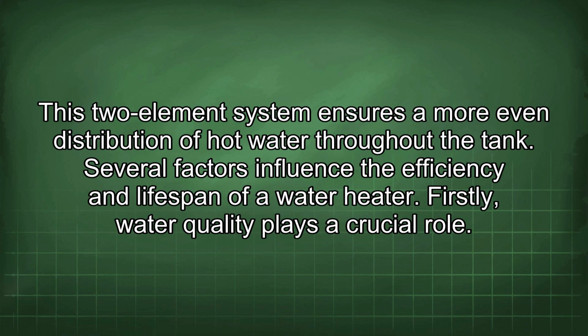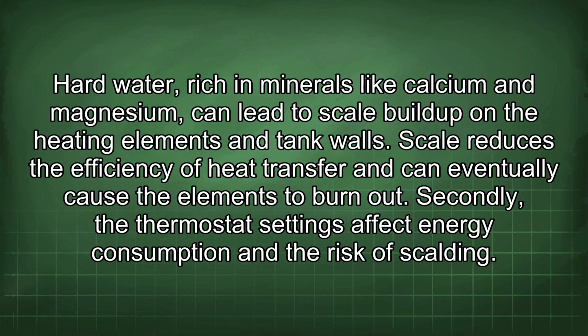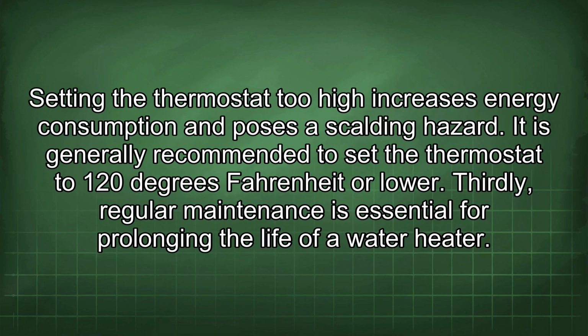Firstly, water quality plays a crucial role. Hard water, rich in minerals like calcium and magnesium, can lead to scale buildup on the heating elements and tank walls. Scale reduces the efficiency of heat transfer and can eventually cause the elements to burn out. Secondly, the thermostat settings affect energy consumption and the risk of scalding. Setting the thermostat too high increases energy consumption and poses a scalding hazard. It is generally recommended to set the thermostat to 120 degrees Fahrenheit or lower.